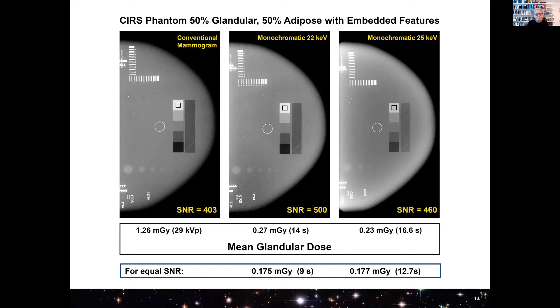The important thing is that the conventional machine delivered 1.26 milligray of dose to the phantom. The mammographic imager at 22 kilovolts delivered 0.27 milligray and 0.23 milligray at 25 kilovolts. If you want to compare them directly, if we had equal signal to noise, 403 for both, this dose of 0.27 would drop to 0.175, and this 0.23 to 0.177, factors of 7 times lower. Now, this is a very, very interesting result with important ramifications.